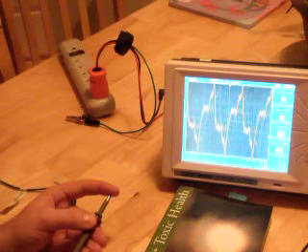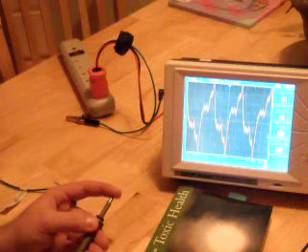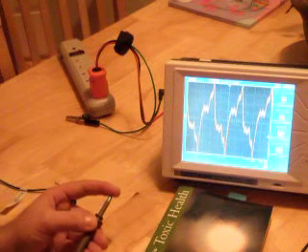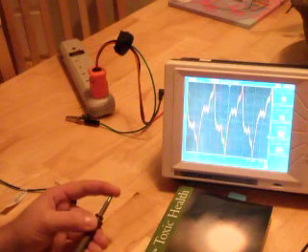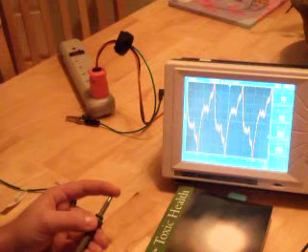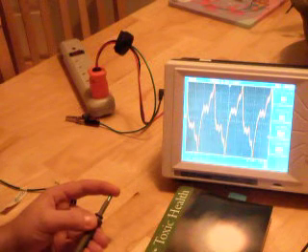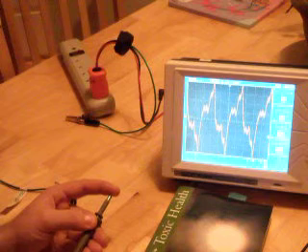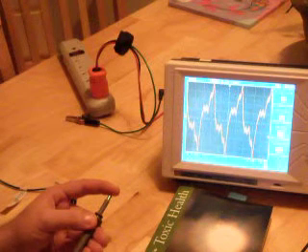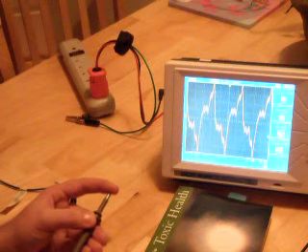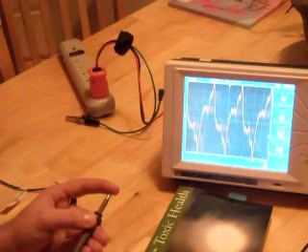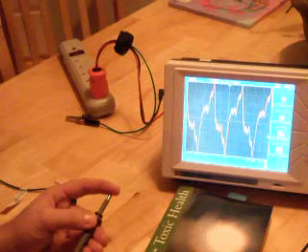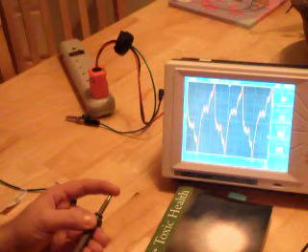The dairy industry has put limits on the voltage that cows can be subjected to, and that voltage is half a volt AC. In my home, the voltage actually peaks at one and a half volts AC. So it's actually three times the allowable contact voltage. As I say, it's throughout the house.